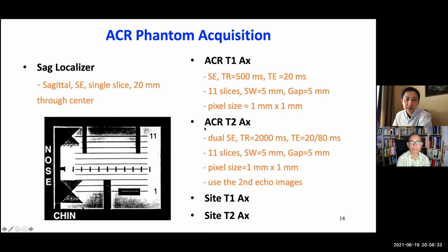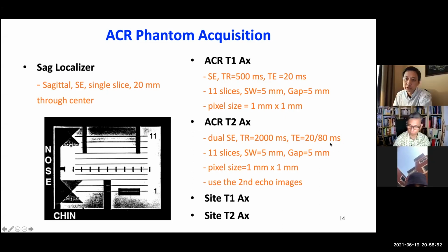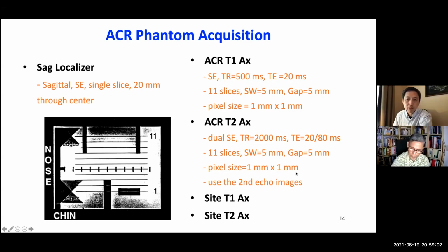And then the ACR T2 is a dual echo spin echo sequence. So there are 2 TEs with a long TR, 2000 TR. And of the 2 TEs, the short TE will be proton density and the long TE will be the T2 weighted image. So we only look at the second TE image, which is the T2 weighted image. The same number of slices and slice location, prescription, and also the same matrix size and resolution.